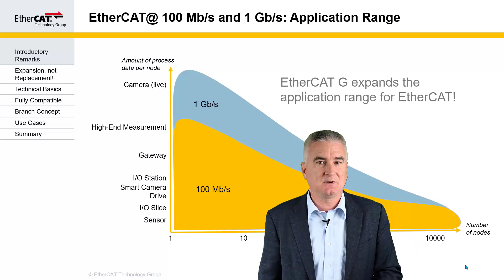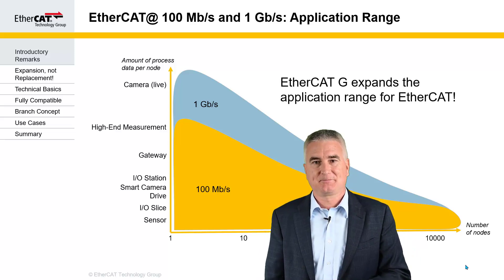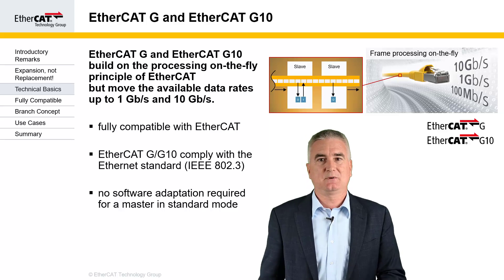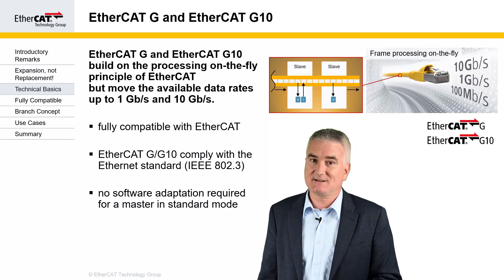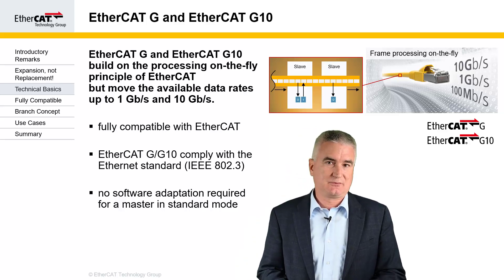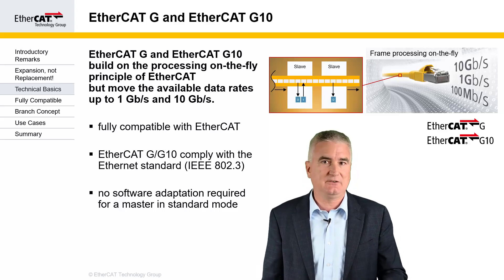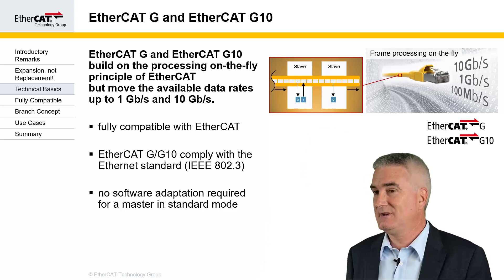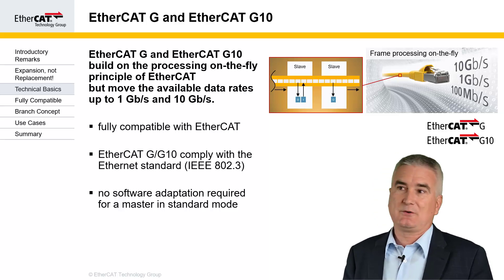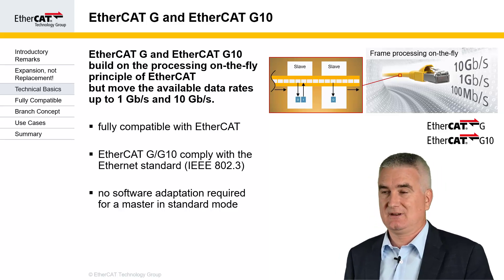At gigabit speed, we have more bandwidth available and we can expand the application range for EtherCAT substantially. EtherCAT-G and G10 use the same functional principle of EtherCAT at 100 megabit per second, but at higher data rates. So it's fully compatible. And of course, we are also fully compatible to the IEEE 802.3 standards using standard Ethernet frames, not changing anything to the frame format. You don't even need to change your software in the EtherCAT master. If you have a gigabit port available, you can run EtherCAT-G in standard mode right away without changing anything in the software.